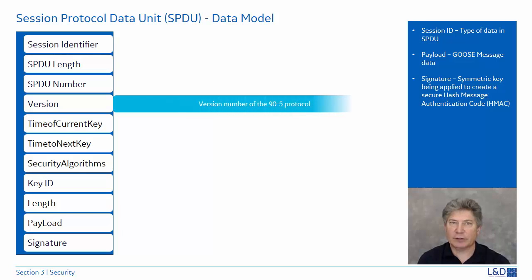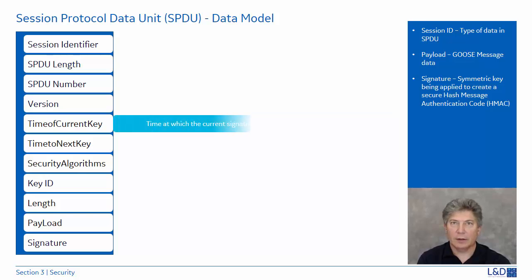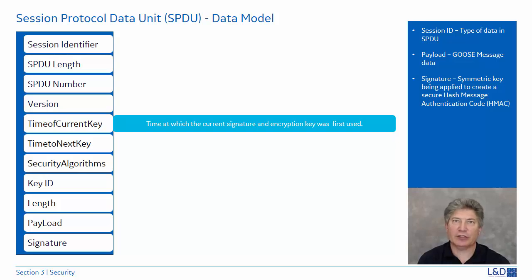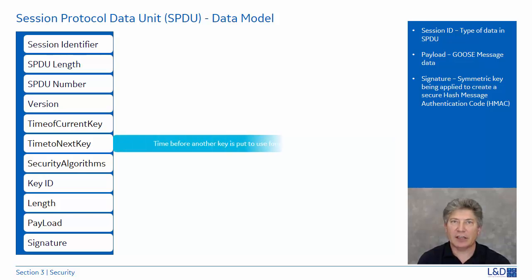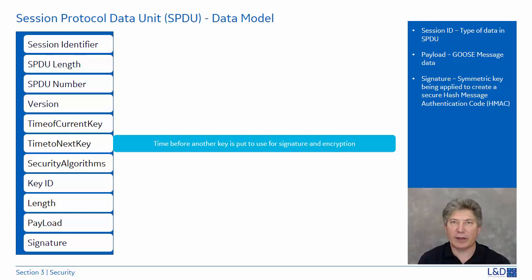The version field indicates the version of the 61850-90-5 protocol being used. The time of current key is a security attribute which represents the time at which the current signature and encryption key was first used. Time to next key is a security attribute that represents the time before another key is put into use for signature and encryption. It is recommended that the Key Distribution Center changes the symmetric keys at least every 48 hours. The value is specified in minutes.